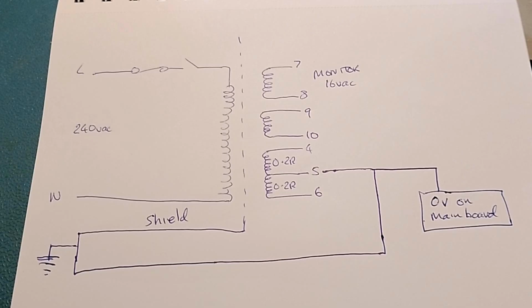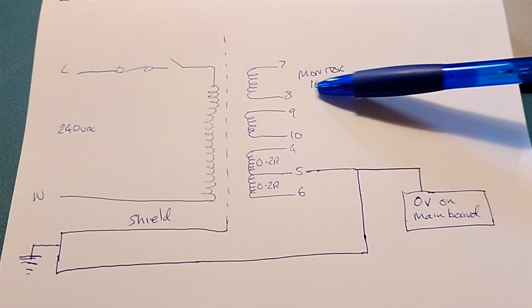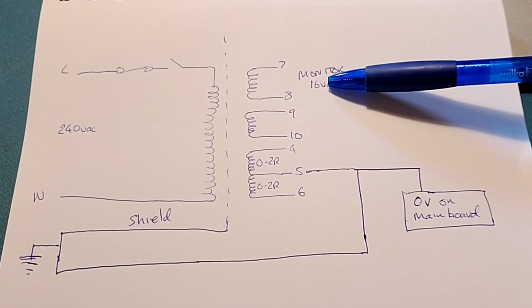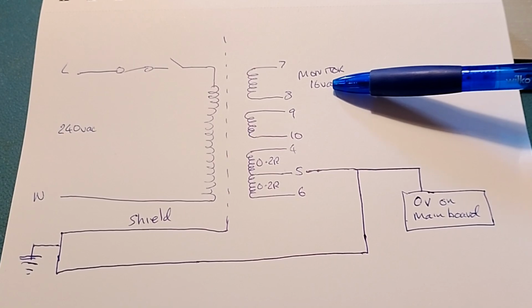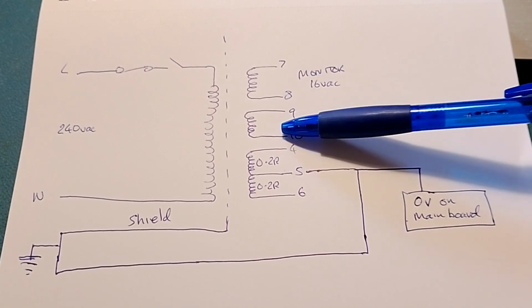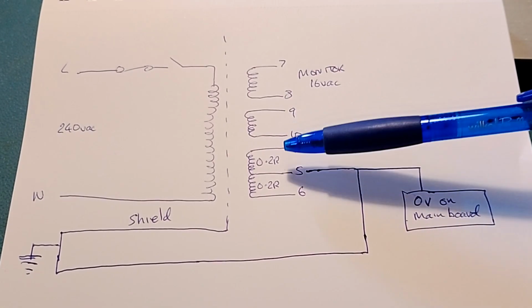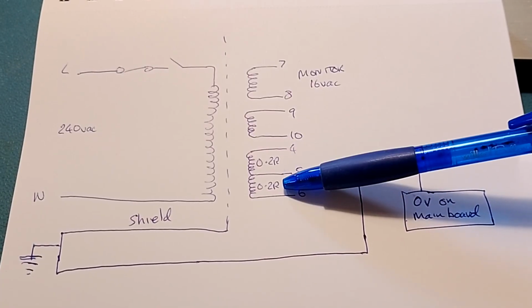I don't know why the trip fired in the first place and why the fuse was taken out, but it hasn't done it since. Pins 7 and 8 go to the monitor on the top of the unit, there's about 16 volts AC out of that winding. This winding here and this centre tap winding go to the main circuit board on the PET.